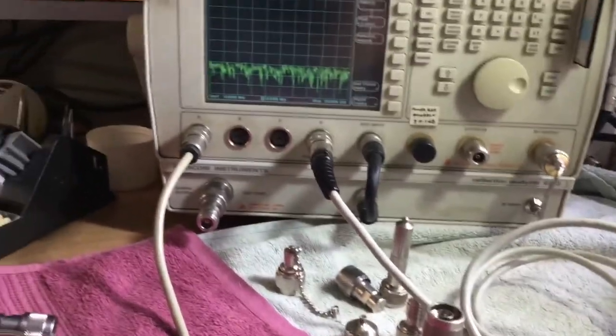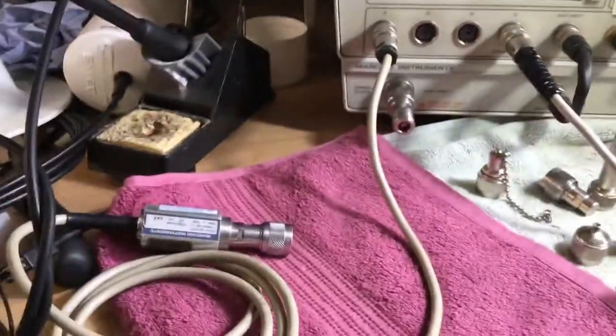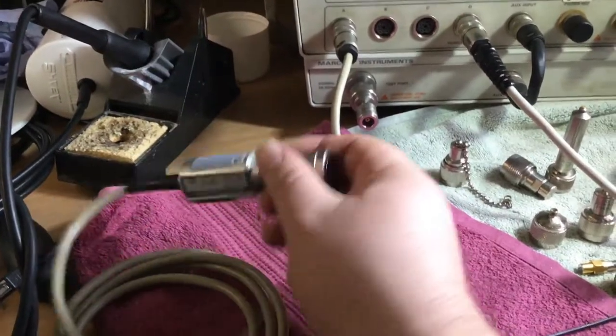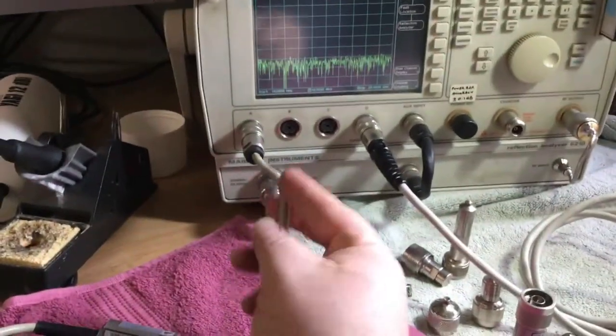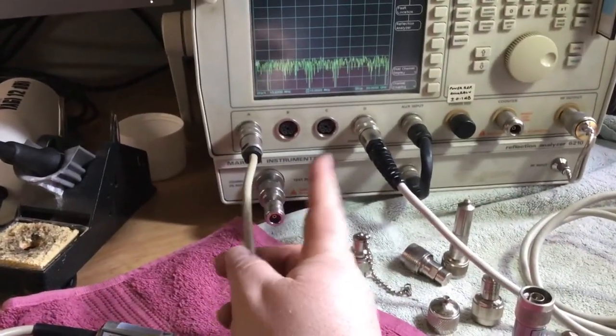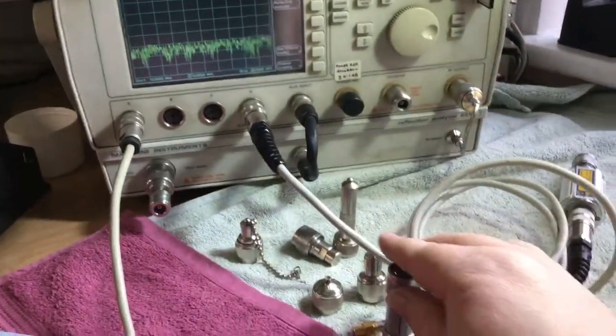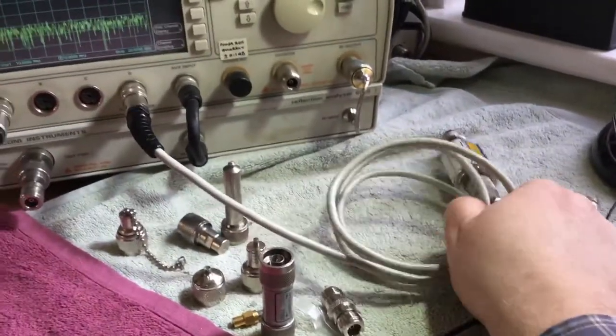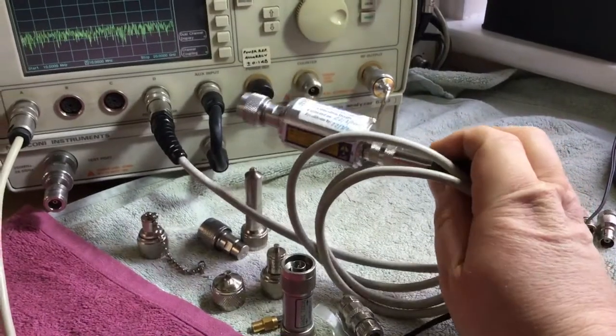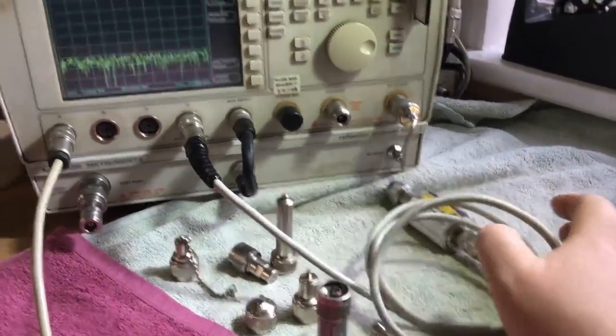And indeed the detectors, the scalar detector which connects into port A, B or C on the front of these, and then the power detectors are these type which connect to port D, and they need calibrating as well.